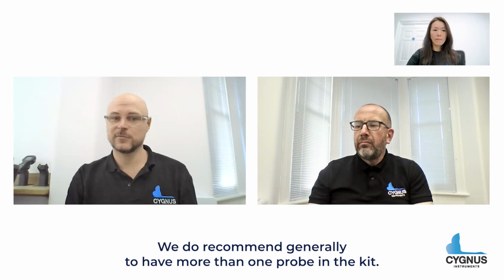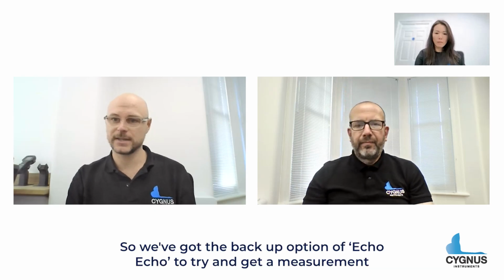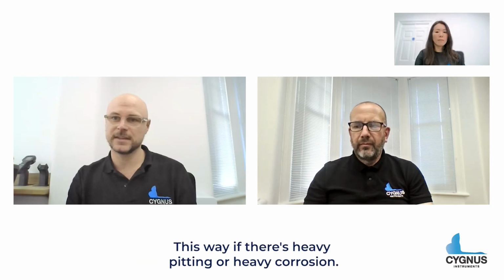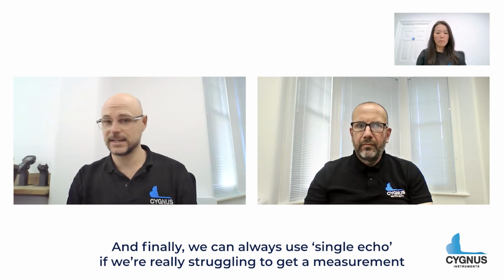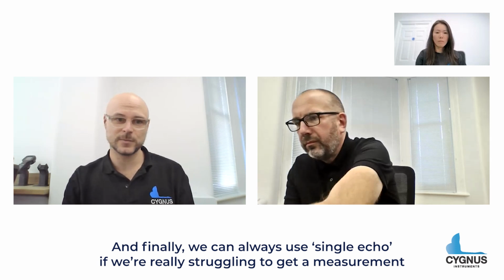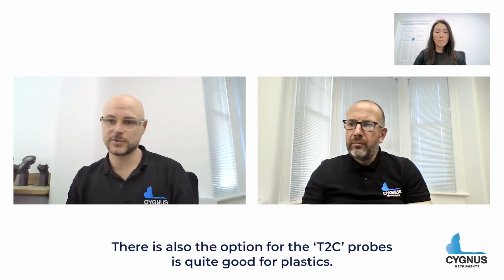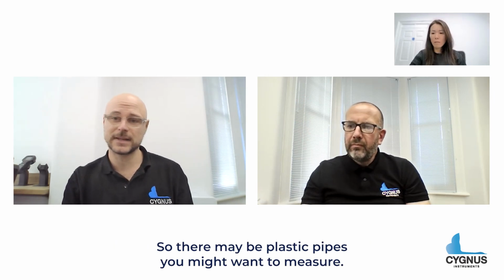We do recommend generally to have more than one probe in the kit, so we'd recommend a twin crystal probe as well, normally the T5B in most situations. So we've got the backup option of echo echo to try and get a measurement this way if there's heavy pitting or heavy corrosion. And finally, obviously we can switch to single echo if we're really struggling to get a measurement because of the level of corrosion. There is also the option for the T2C probe, which is quite good for plastics. So there may be plastic pipes you may want to measure. We recommend the T2C in that situation. Okay, thank you.